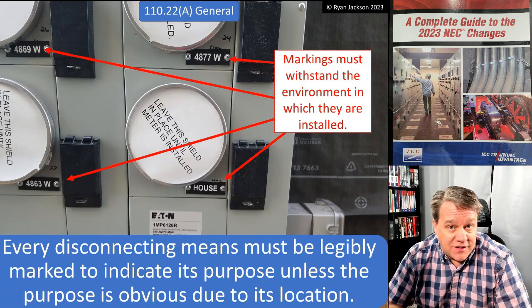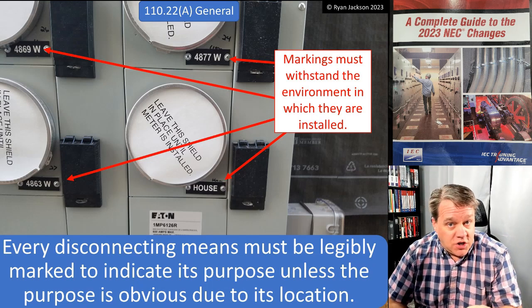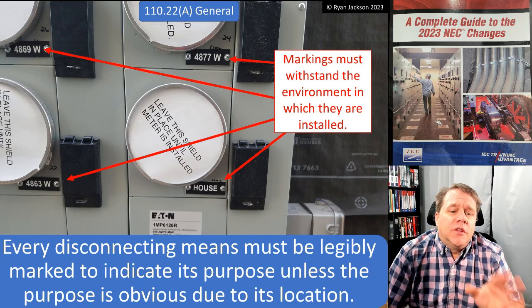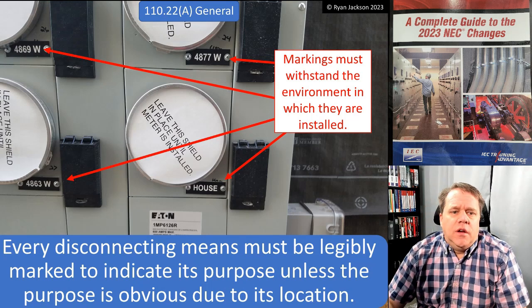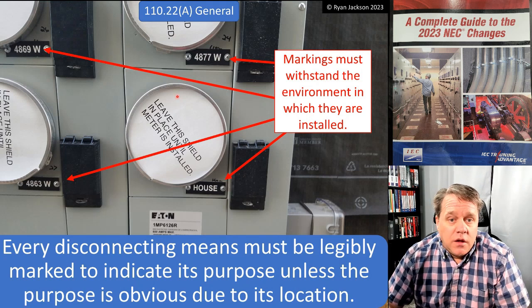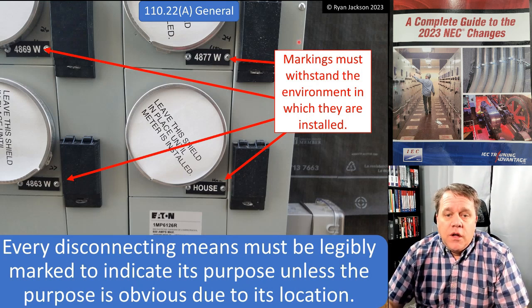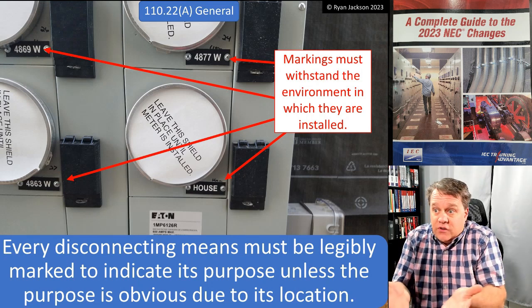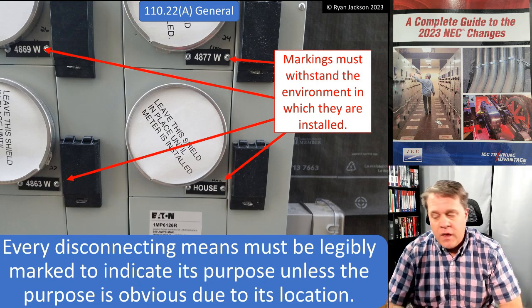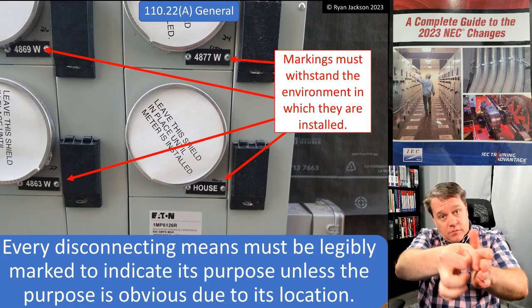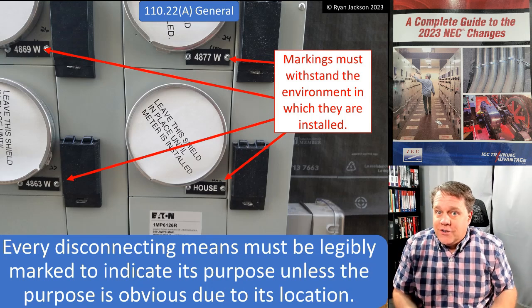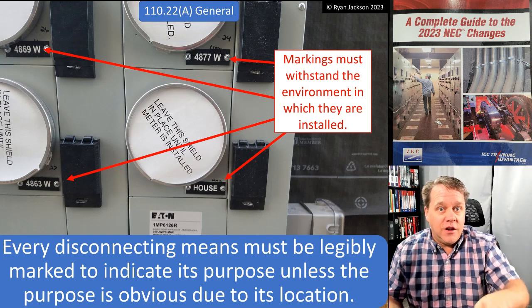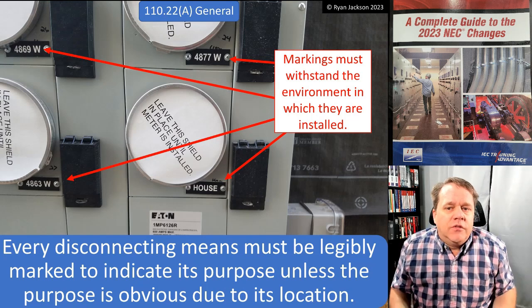110.22(a) did not change. It says every disconnecting means must be legibly marked to indicate its purpose, unless the purpose is obvious due to its location. Here I have a multi-family dwelling with three different units and a house meter, so we have to tell people what each disconnecting means is doing - unless it's obvious. For example, if you walk up to a disconnect outside and you can see liquid-tight conduit terminating to an air conditioner, it's pretty obvious that's the AC disconnect, so you don't have to mark it.